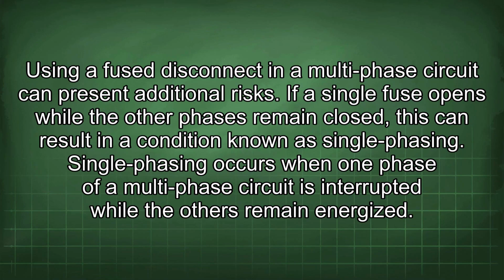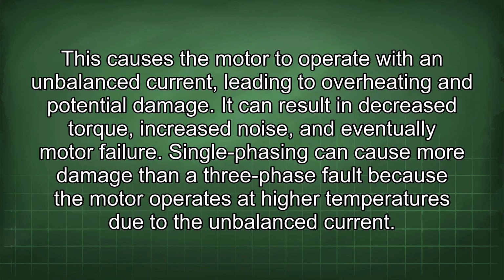Using a fuse disconnect in a multi-phase circuit can present additional risks. If a single fuse opens while the other phases remain closed, this can result in a condition known as single phasing. Single phasing occurs when one phase of a multi-phase circuit is interrupted while the others remain energized. This causes the motor to operate with an unbalanced current, leading to overheating and potential damage.